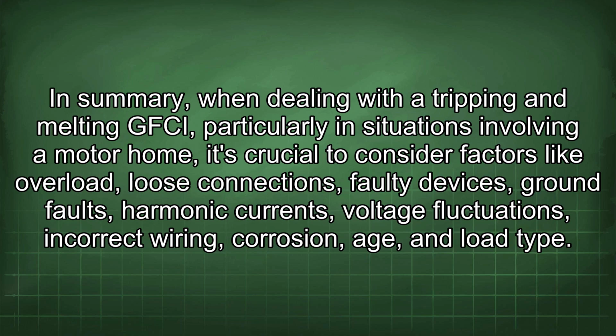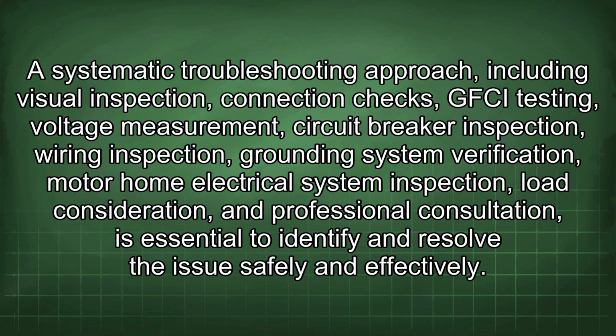In summary, when dealing with the tripping and melting GFCI, particularly in situations involving a motorhome, it's crucial to consider factors like overload, loose connections, faulty devices, ground faults, harmonic currents, voltage fluctuations, incorrect wiring, corrosion, age, and load type. A systematic troubleshooting approach, including visual inspection, connection checks, GFCI testing, voltage measurement, circuit breaker inspection, wiring inspection, grounding system verification, motorhome electrical system inspection, load consideration, and professional consultation is essential to identify and resolve the issue safely and effectively.